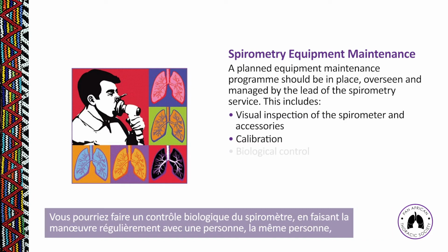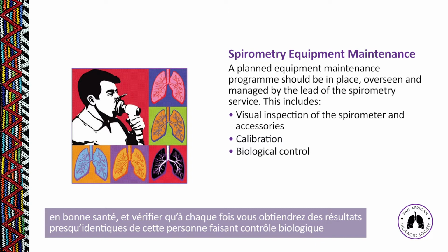You could do biological control on the spirometer, which is when you use a healthy, normal person to blow onto the machine on a regular basis and make sure that almost exactly the same results are read every single time that same biological control person blows.